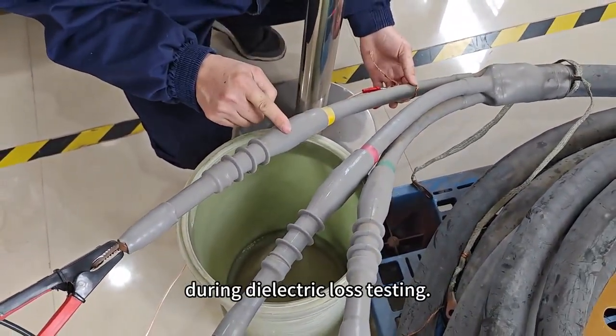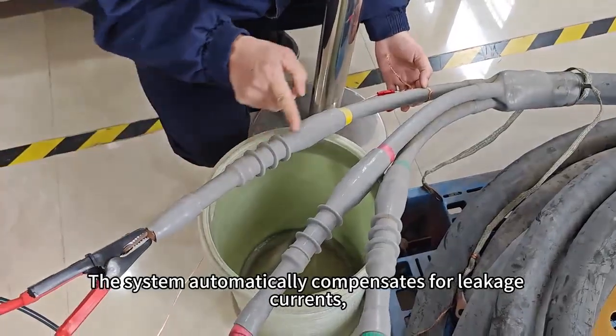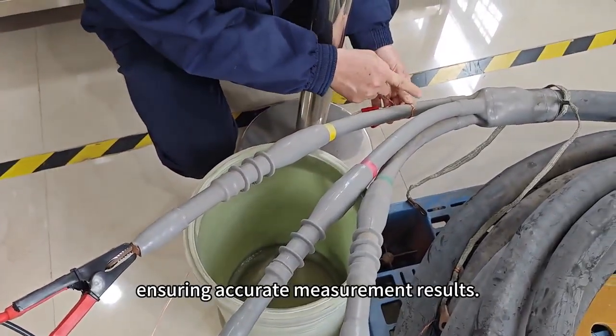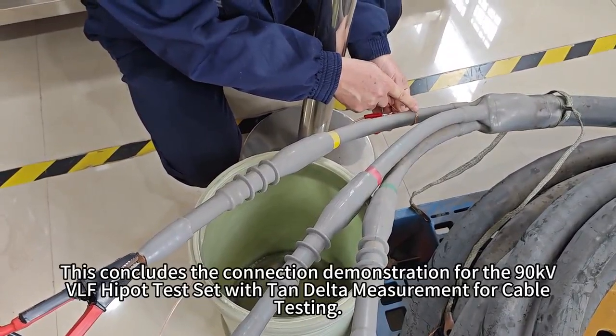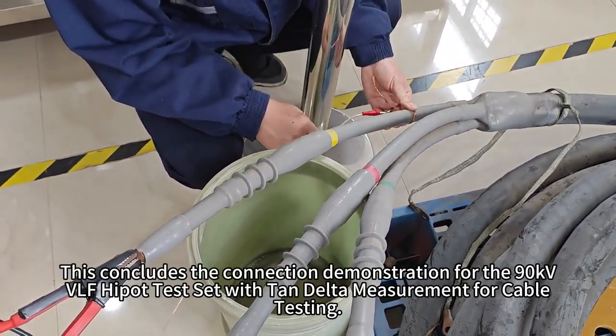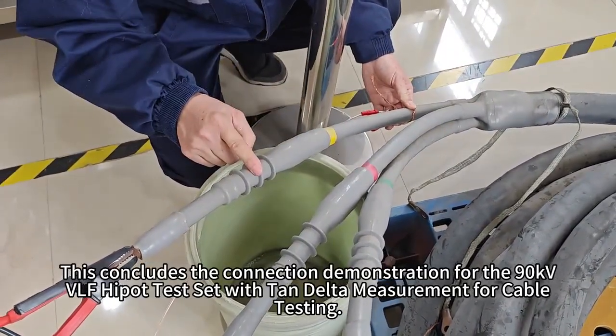During dielectric loss testing, the system automatically compensates for leakage currents, ensuring accurate measurement results. This concludes the connection demonstration for the 90 kV VLF Hipot test set with Tan Delta measurement for cable testing.